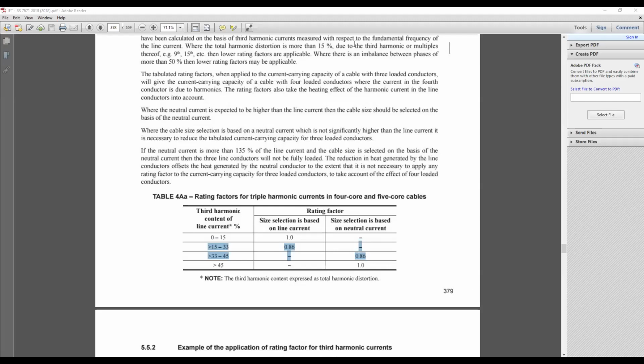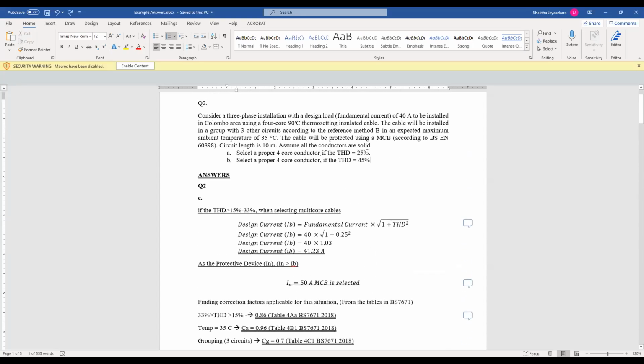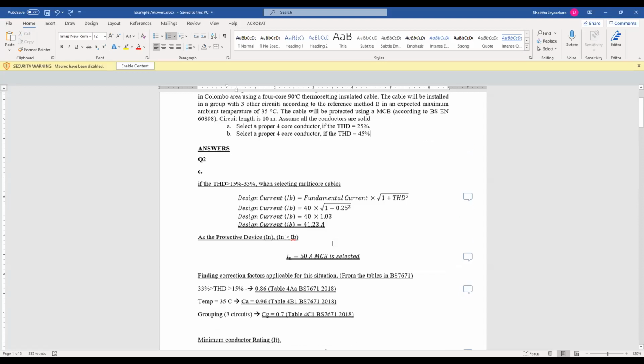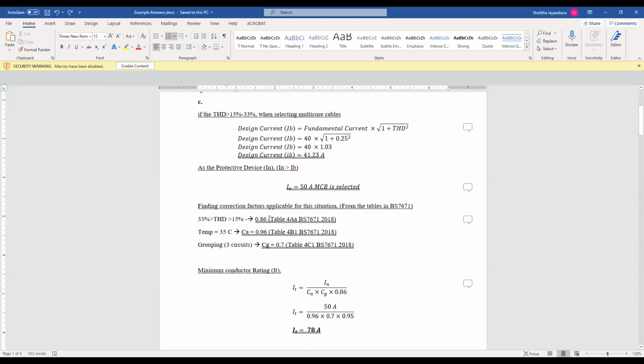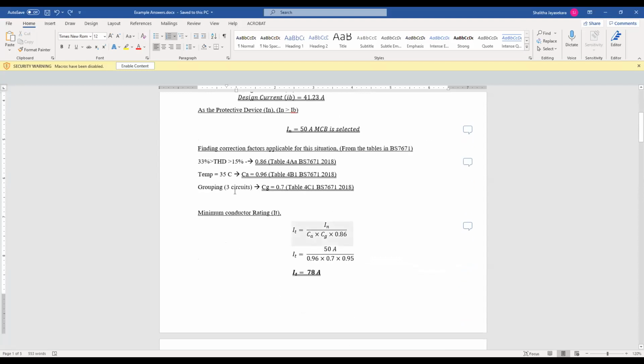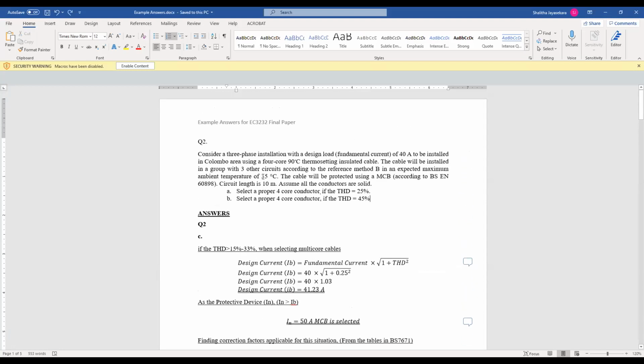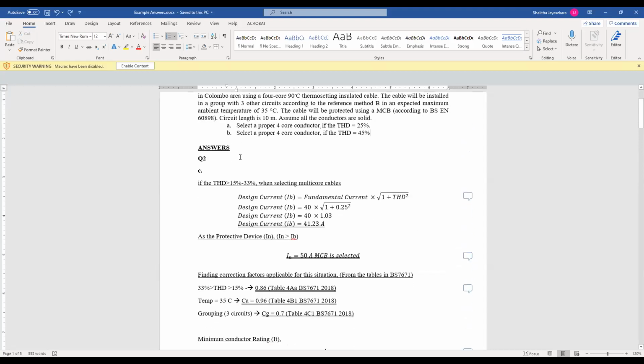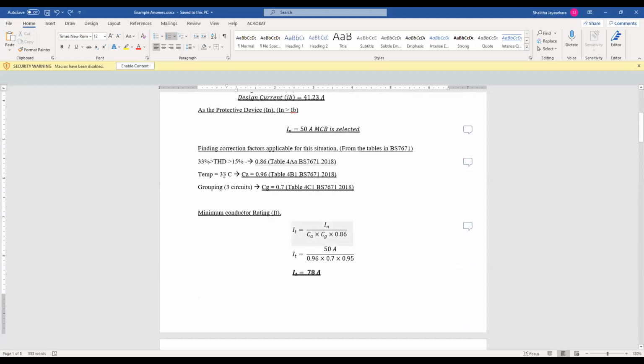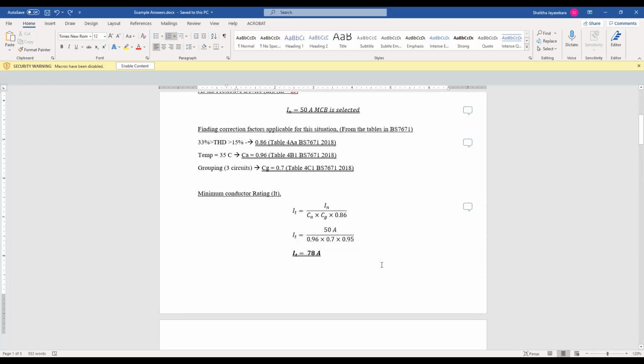So in this case, our percentage is 25. That means our third harmonic content is in between 15 and 33. So we have to add another rating factor. So see, it is less than 33 and higher than 15, and 0.86 rating factor will be there. So this is additional to the other rating factor. So in here we have ambient temperature as 35, and grouping we have three other circuits. So grouping we have this rating factor, temperature we have this rating factor, and additionally third harmonic content will introduce this rating factor. So you guys know this equation.